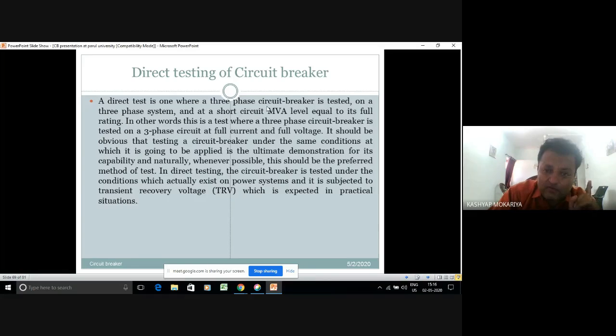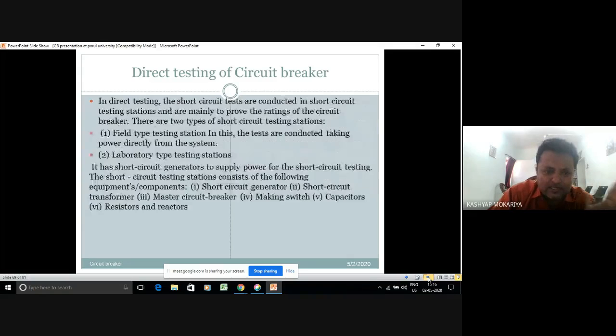A direct test is one where a three-phase circuit breaker is tested on a three-phase system and at a short circuit MVA level equal to its full rating. In other words, this is a test where a three-phase circuit breaker is tested on a three-phase circuit at full current and full voltage. It should be obvious that testing a circuit breaker under the same conditions in which it is going to be applied is the ultimate demonstration of the capability of the breaker. I will show you the diagram while discussing all those things.